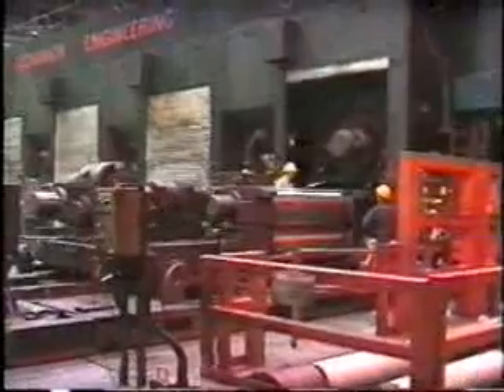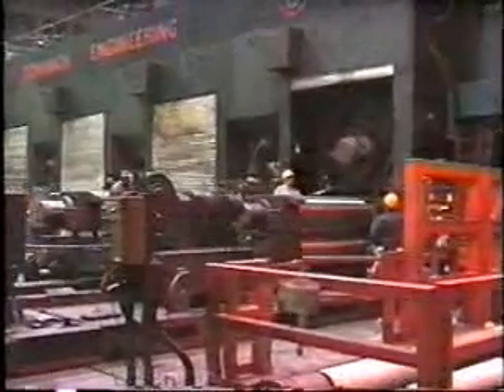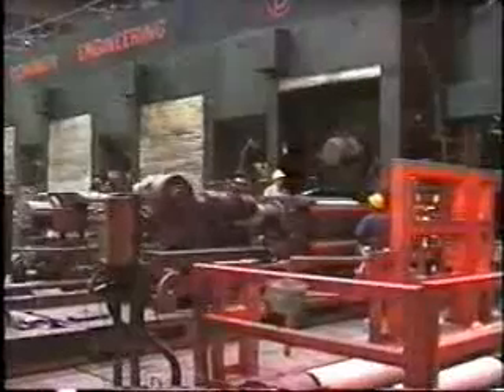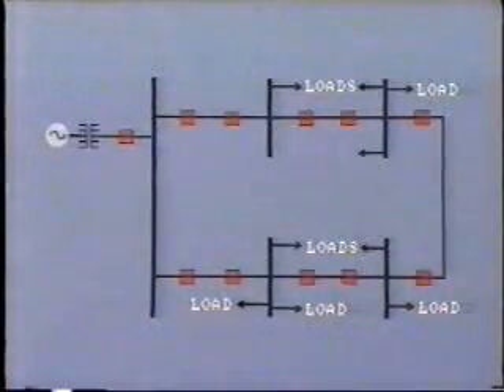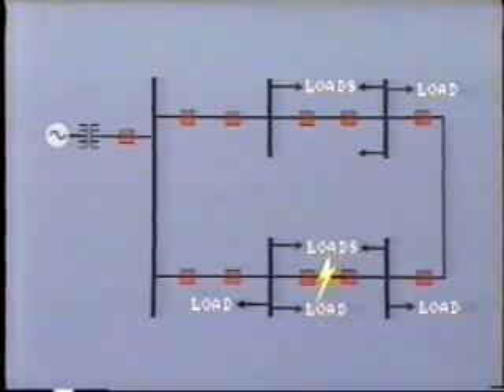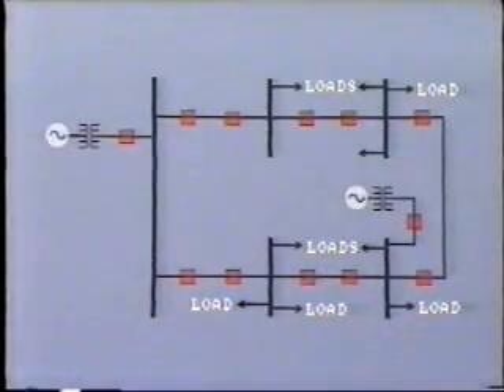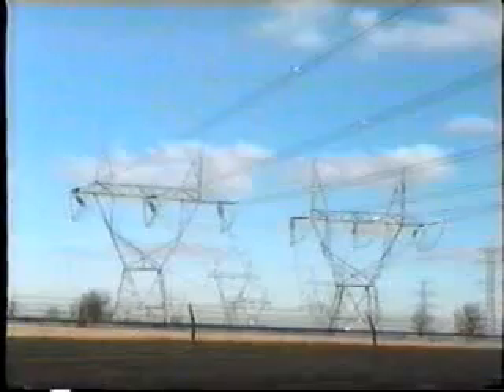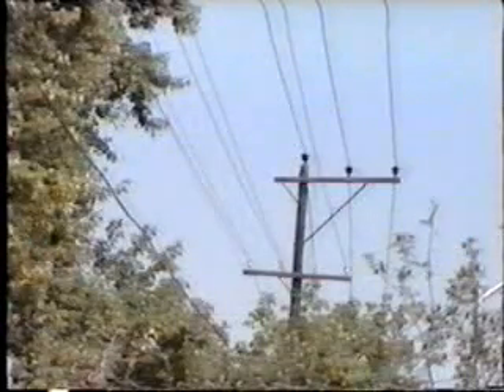In some systems, large industrial consumers are fed directly from this sub-transmission system at high voltage. The advantage of the loop is that in case of a fault, say here, this faulty section of line can be isolated by opening the breakers at each end, while the loop continues to supply the remainder of the customers. In some loop systems, a further source of supply may be added so as to increase reliability. The sub-transmission lines provide the link between the high-voltage bulk transmission system and the various distribution stations.